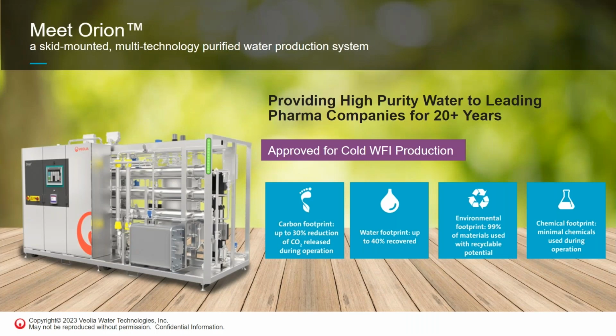So how do we do it? Well, some of you may or may not have seen our Orion product. The Orion product is predominantly a generation system, based around softening, RO and EDI. By the addition of a UF on the back end of the EDI, we can produce WFI quality water. So we have a twin membrane system there with the RO and the UF membranes. And this particular product has been around for 20 years. We're on the Mark III iteration of it.